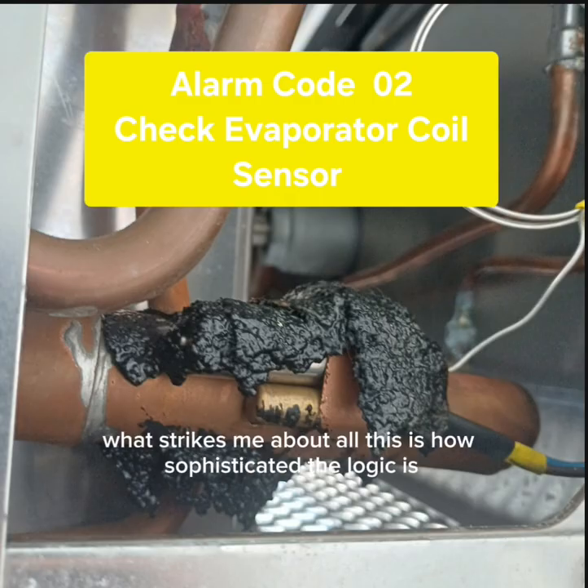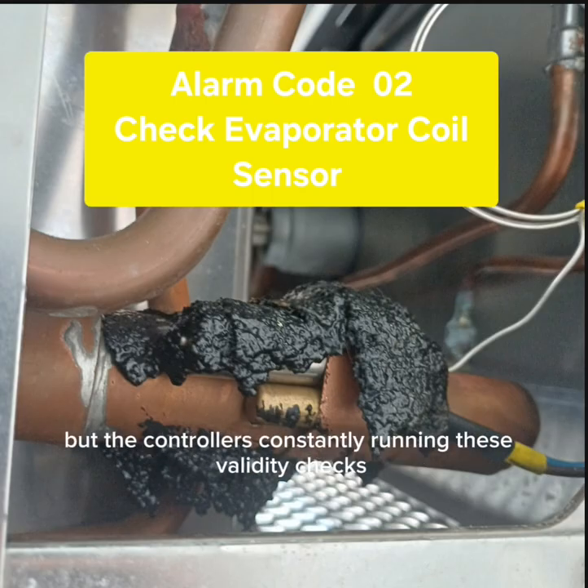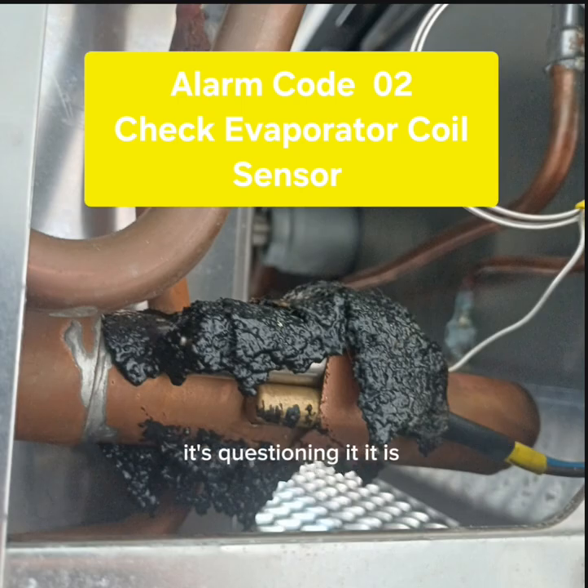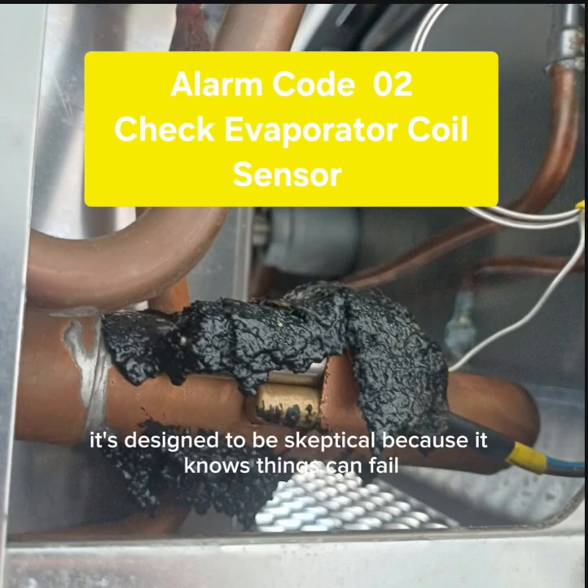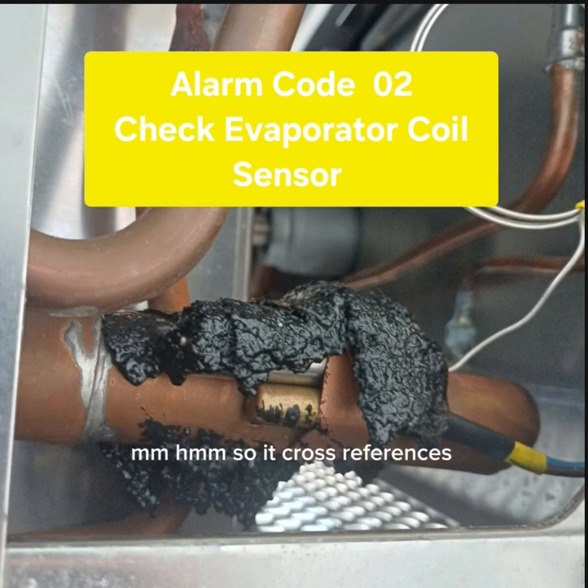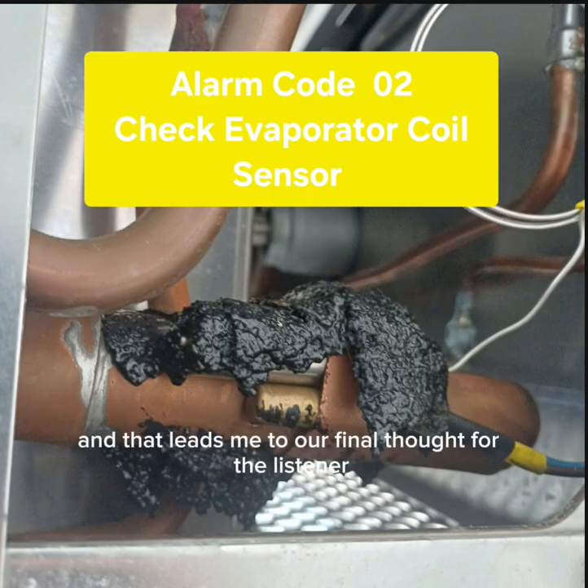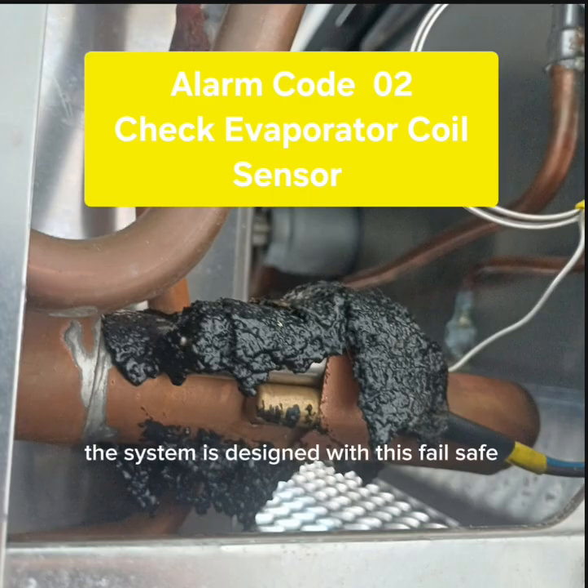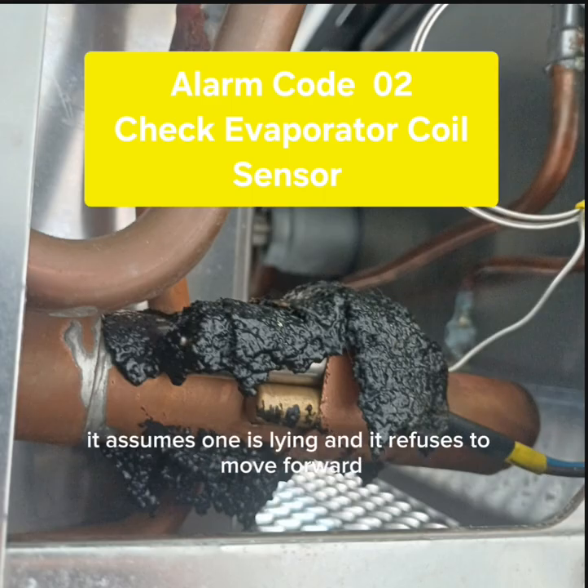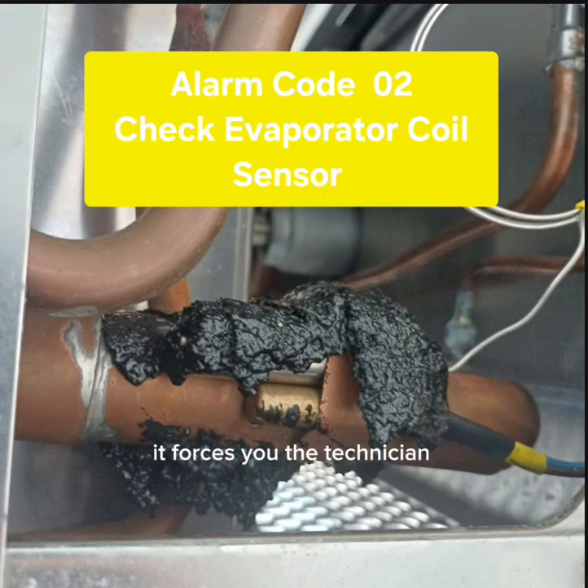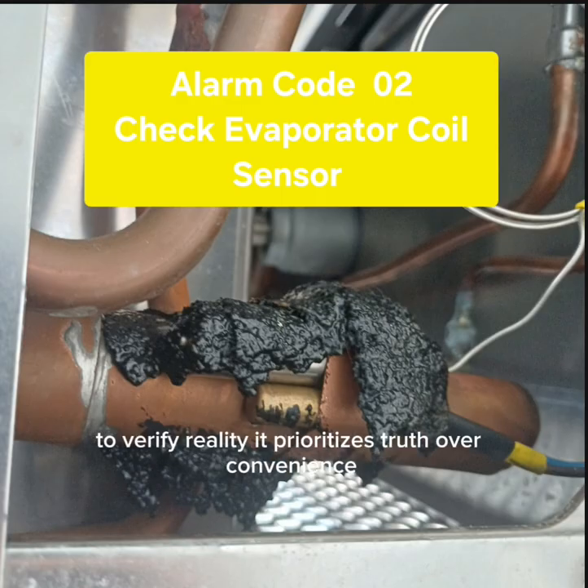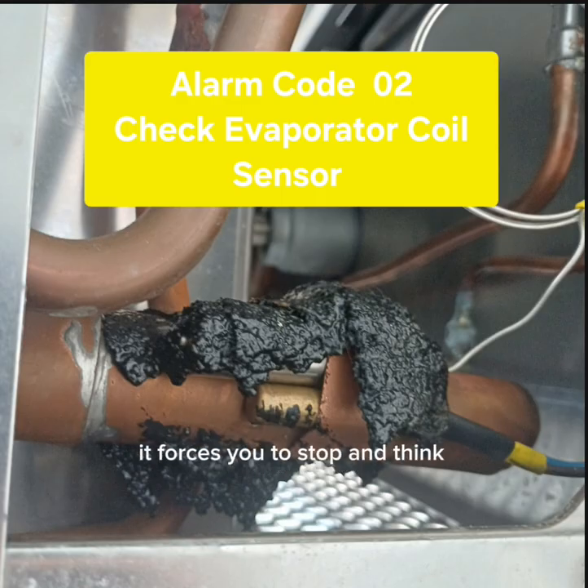You know, what strikes me about all this is how sophisticated the logic is. We think of these as just big freezers, but the controller is constantly running these validity checks. It's not just taking data blindly, it's questioning it. It is. It's designed to be skeptical because it knows things can fail. So it cross-references, it's checking its own work all the time. And that leads me to our final thought for the listener. The system is designed with this fail-safe. If 3 sensors don't agree, it assumes one is lying and it refuses to move forward. It forces you, the technician, to verify reality. It prioritizes truth over convenience. It forces you to stop and think.